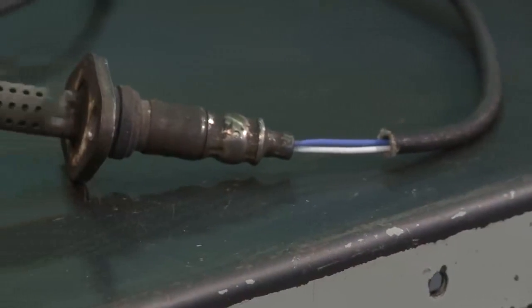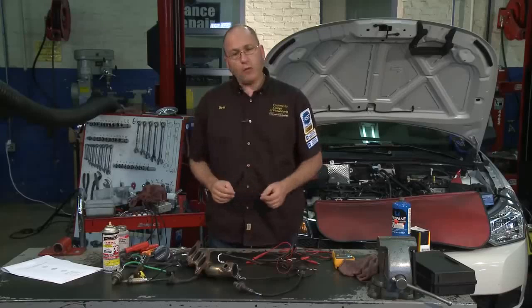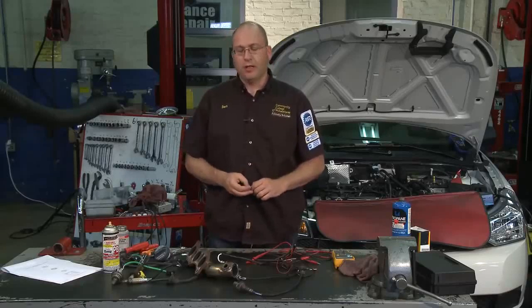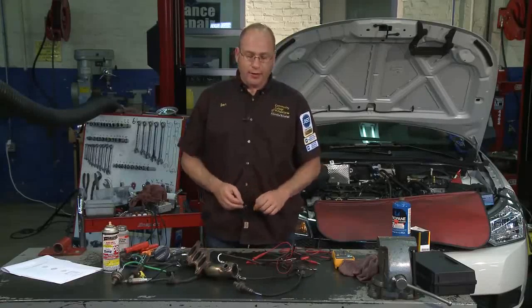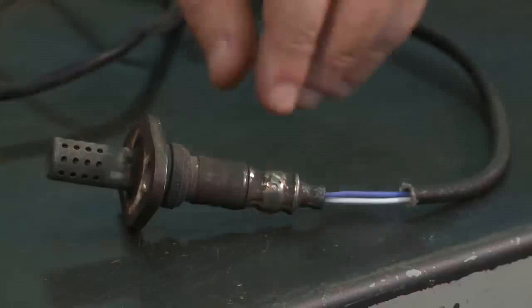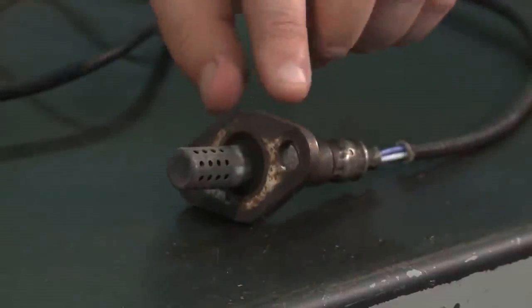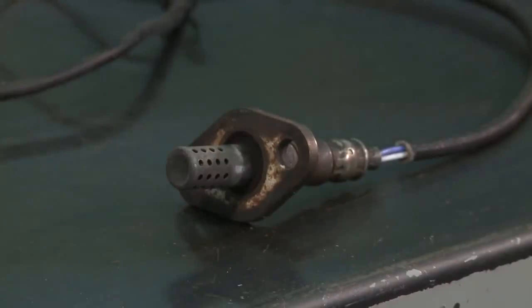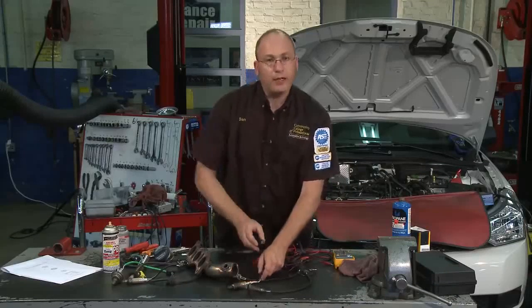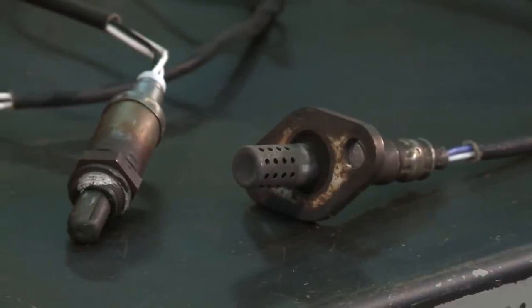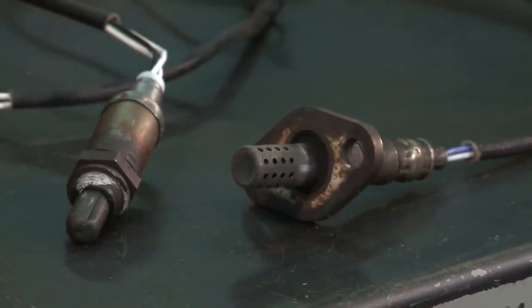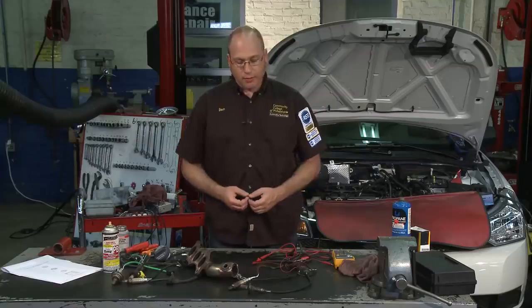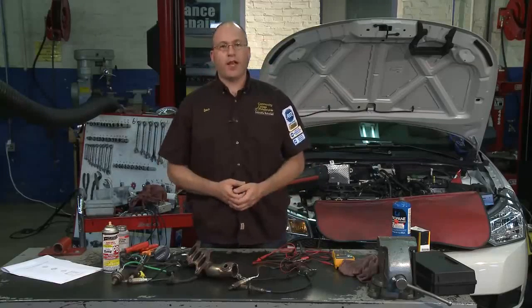It's sort of like a miniature toaster oven. And that worked pretty well until manufacturers realized that the power that we were sending through this guy had to be returned through this rusty flange or a rusty fitting back through a rusty exhaust manifold, and the heaters were not working and the sensors were not as accurate as they could be. So what did manufacturers do?